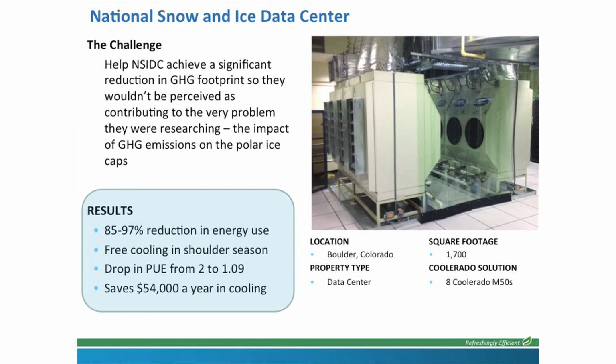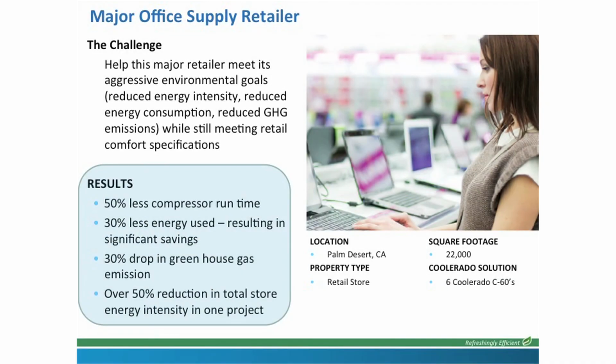Very, very cool. Plus, one extra feature of this is I mentioned that the working air from our unit here is a saturated airflow. That means it's humid, just like a swamp cooler would be. In this case, we can take some of that airflow and put it into the data center so that when it gets too dry outside, we can increase the humidity level inside the data center, which is advantageous because you want to avoid static inside the data center. So potential uses for that airflow.